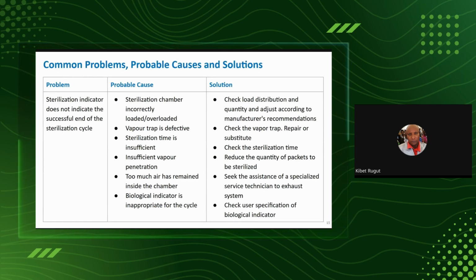So what can cause that? The chamber may be incorrectly loaded or overloaded, so steam is not circulating well. The vapor trap is defective, so it's releasing vapor to the air. You find vapor at the back of the autoclave just going up into the atmosphere. And the sterilization time is insufficient. Maybe you put 15 minutes instead of 21, and so forth.